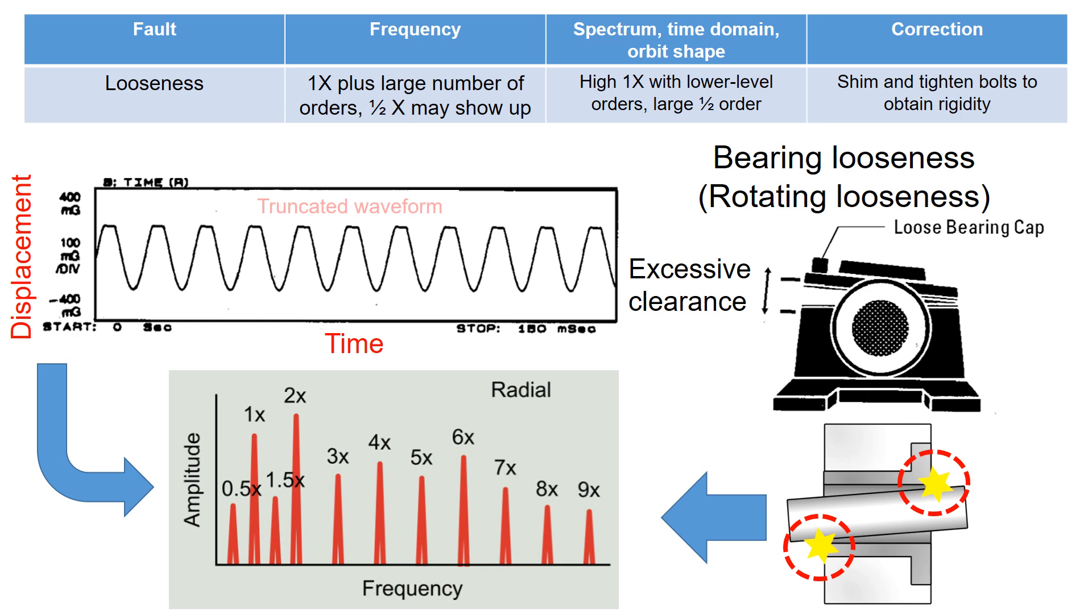So, returning to this slide, if your machine vibration measurements display multiple harmonics—1x, 2x, 3x, and so on—in the frequency spectrum, it indicates the presence of rattling motion within the machine.